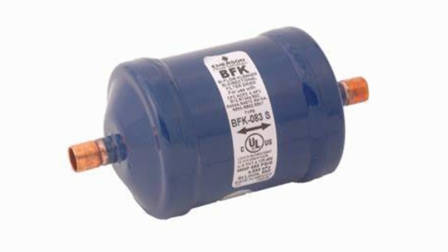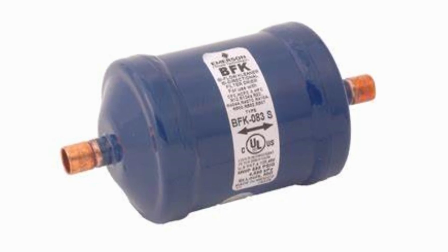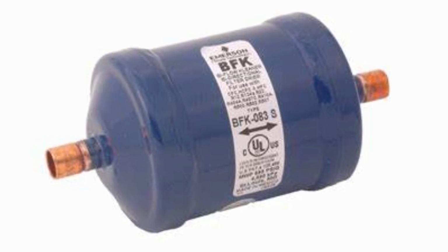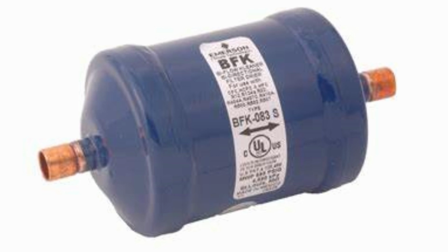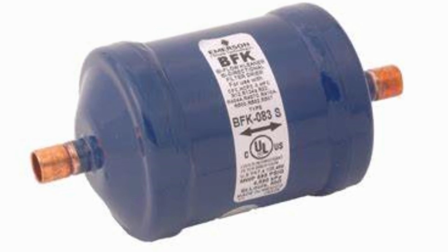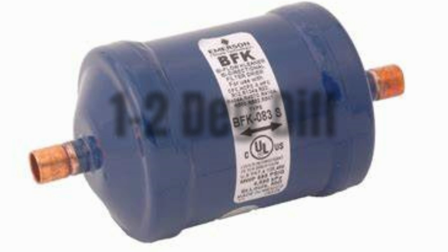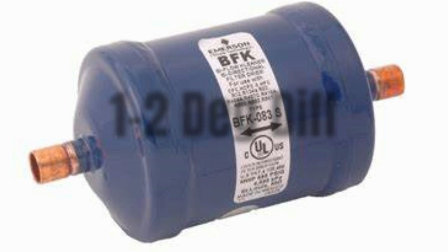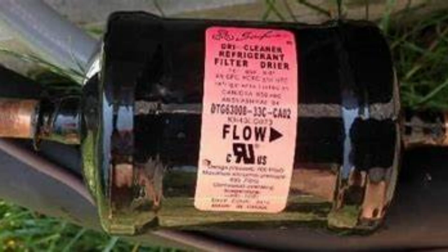The next two measurements, you may or may not have one, but if you have a filter dryer in the smaller copper line, you just want to measure both sides of that filter dryer, immediately on one side and the other. If you see any more than a 1, maybe 2 degree difference, that could be an indicator that the filter dryer is plugged and you have a problem with flow in your refrigeration cycle. Now these filter dryers, many times you'll find them right outside on the smaller line set on the condensing unit outdoors.